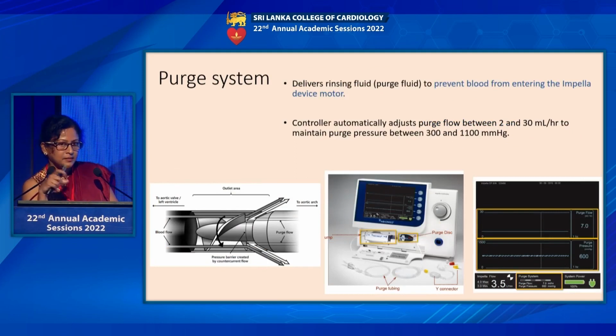So the third system is the purge system. The objective of the purge system is to protect the motor, because blood is ejected at the motor, and if it gets here, it can clot and damage the motor, so it will not work.